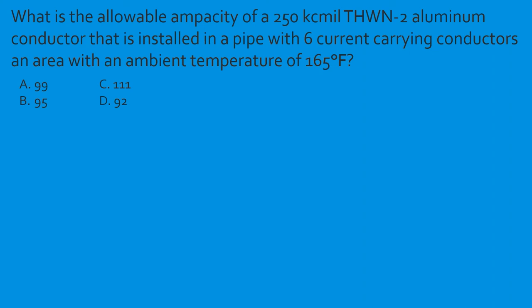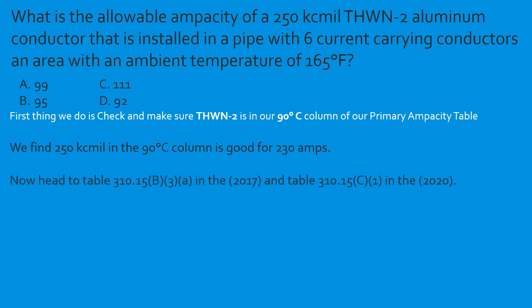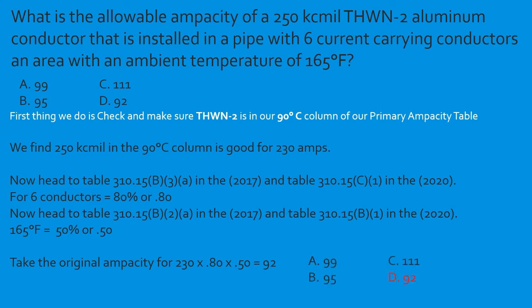Question: What is the allowable ampacity of a 250 kcmil THWN-2 aluminum conductor installed in a pipe with six current-carrying conductors in an area with an ambient temperature of 165°F? Confirm insulation is in the 90°C column. 250 kcmil aluminum is 230 amps. Six conductors — bundling adjustment factor is 0.80. Temperature at 165°F — correction factor is 0.50. So: 230 × 0.80 × 0.50 = 92 amps. Select D.